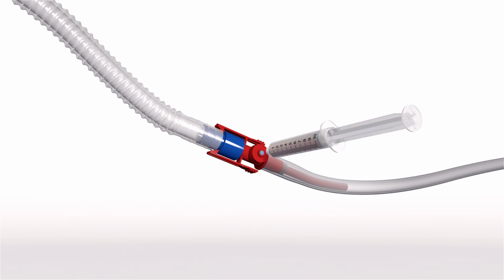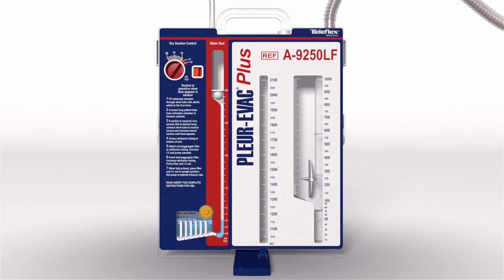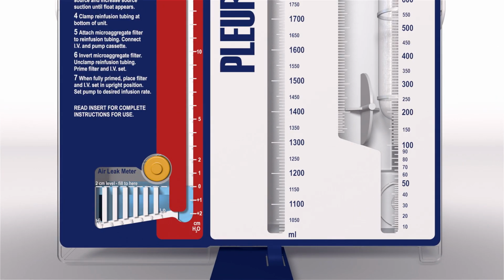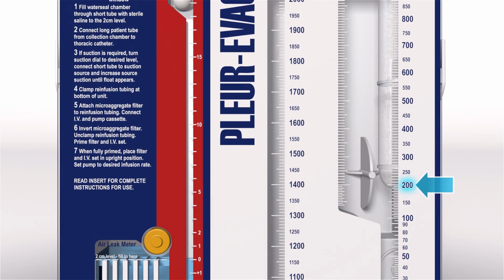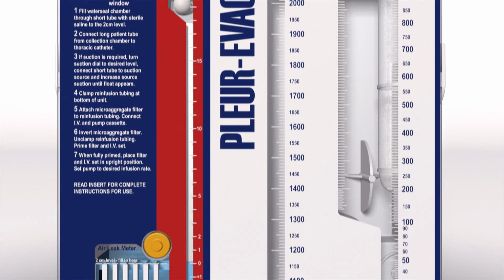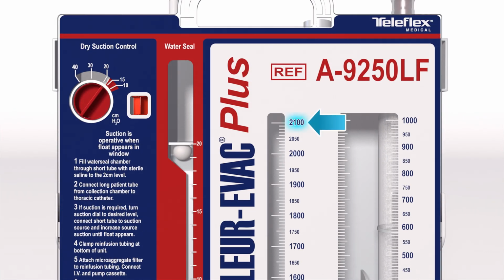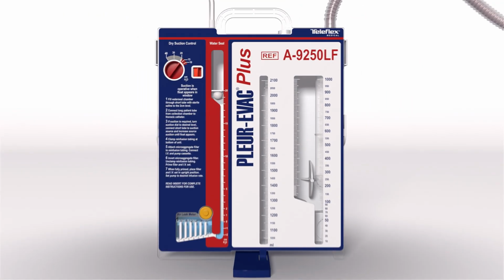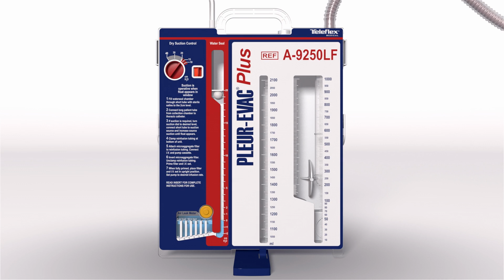No needle is required. The collection chamber of the A9250LF is calibrated in 2 milliliter increments up to 50 milliliters, in 5 milliliter increments up to 200 milliliters, and 10 milliliter increments up to 2,100 milliliters. Only contents within the first collection chamber can be used for reinfusion. A 200 micron screen filter is contained within this chamber.